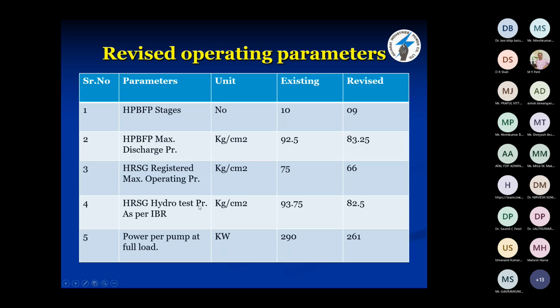As per IBR, every year at the annual inspection, we have to provide the HRSG for hydro test. The hydro test is carried out at 1.25 times the maximum design pressure. Earlier, it was to be carried out at 93.75 kg, 75 kg into 1.25 comes to 93.75. Now we have revised it to 66 kg. Now we have to give the hydro pressure at 82.5 kg, because after the stage reduction, my pump will have a maximum discharge pressure of 83.25 kg only. So I cannot give much higher pressure. So now I have to give the hydro test at 82.5 kg pressure only.